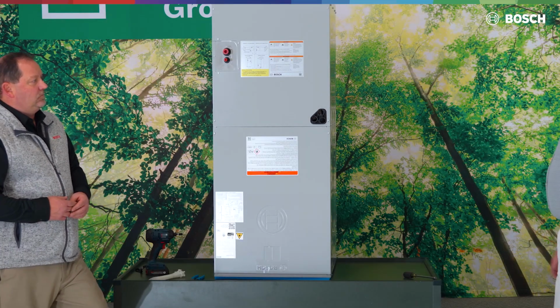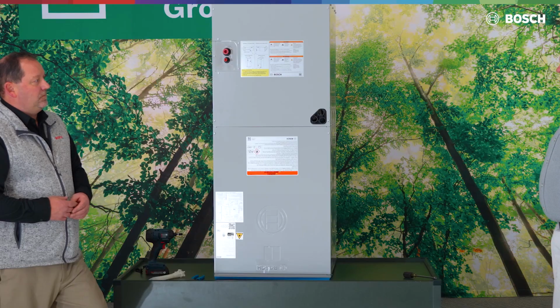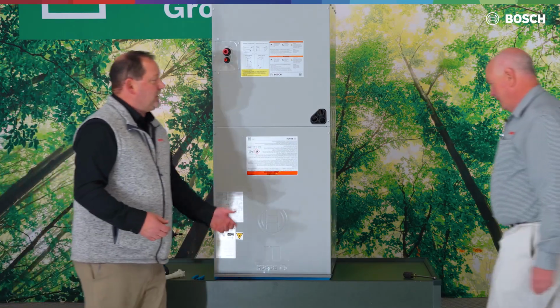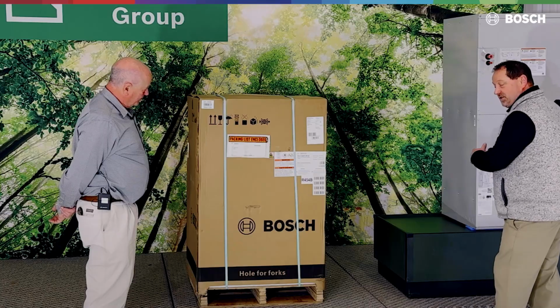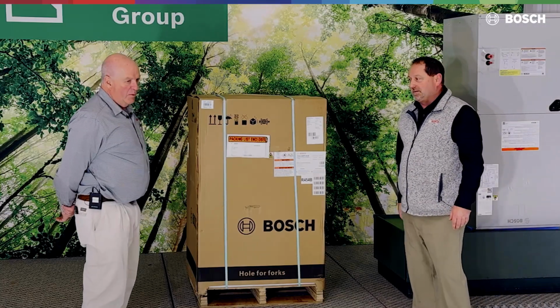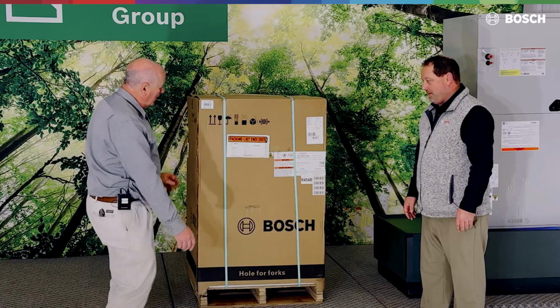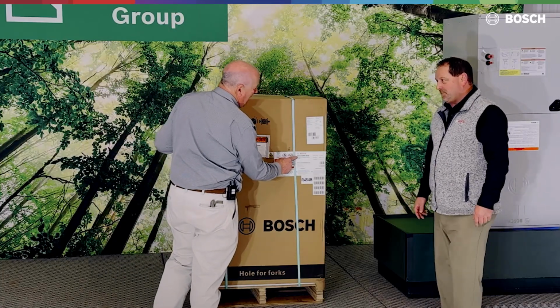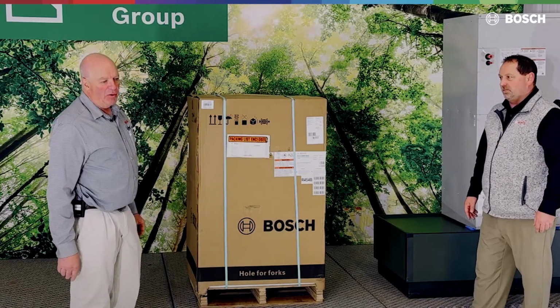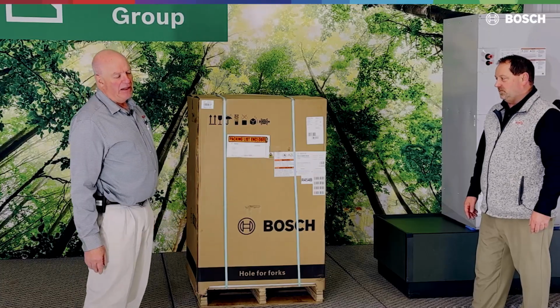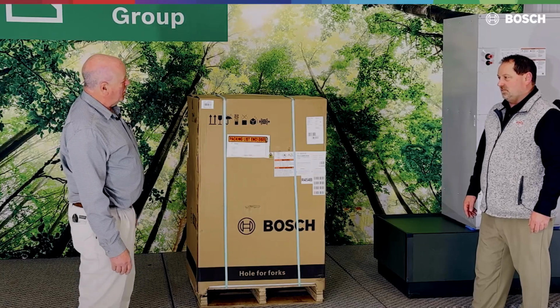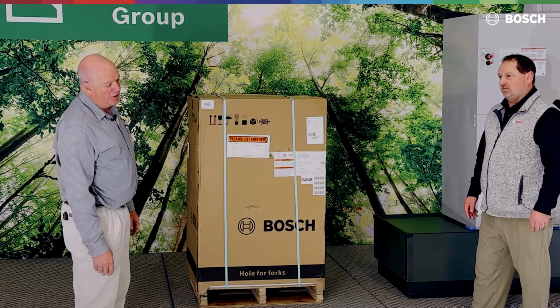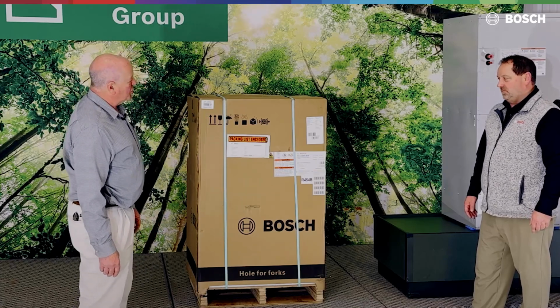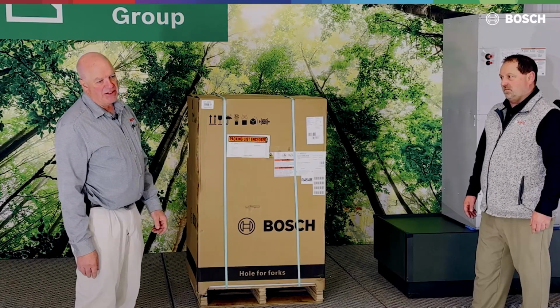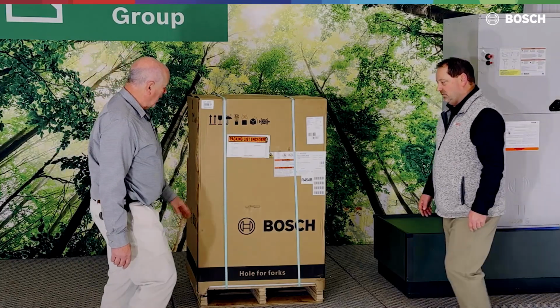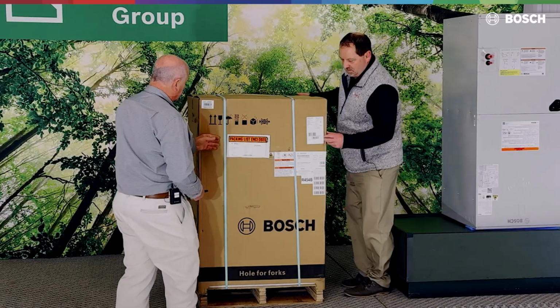Okay. All right. Why don't we go and see what the compressor section looks like? Maybe we uncrate that. Let's go unbox that. Absolutely. Now that we've got the indoor section taken apart, we're going to work on the outdoor unit. And once again, before we start, we want to make sure we have the correct model number and capacity. It really stinks when you haul this unit down the stairs and something doesn't fit. There is a lot of information on our website. You can download either the brochure, an IOM, or an engineering submittal sheet with specifications for sizes so we know what we're dealing with before we open it. So we are good on this one. We're going to go ahead and uncrate this one as well.